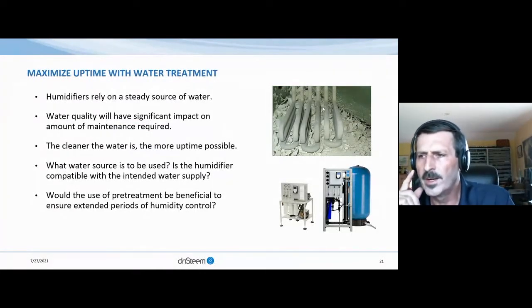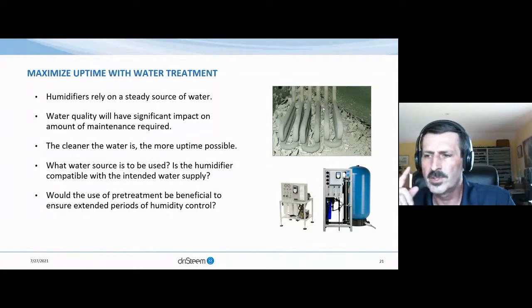Humidification depends on water and equipment and is at the mercy of the water you choose to feed it. Simple operation and the amount of maintenance is directly related to water quality. The use of water treatment is highly recommended. Water treatment can reduce maintenance requirements, which in turn reduce equipment downtime, as well as prevent any unintended equipment failures. Fortunately, most pharmaceutical facilities will have processed water available. We should also note that in addition to water treatment for mission-critical systems, redundant systems should be considered.